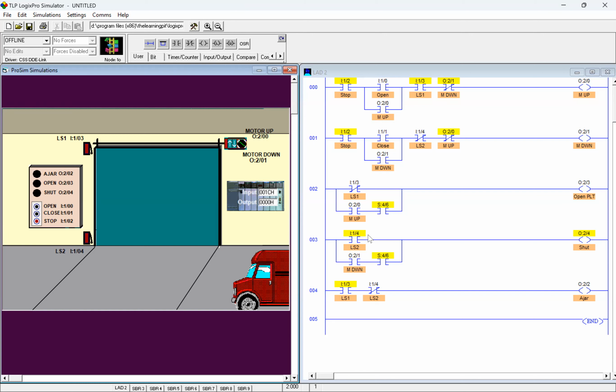All right. First one's easy. If it's in motion, that either means my motor up or my motor down, one of the two. Their contacts are on, right? They're active. So if either one of them is active, then I've got that thing steady on. Also, I have to be in between these limit switches, right? So this and whatever condition I'm on is going to happen.